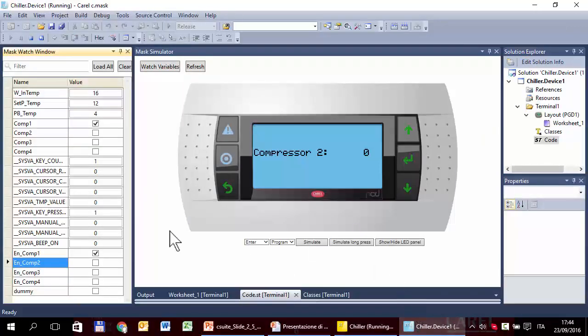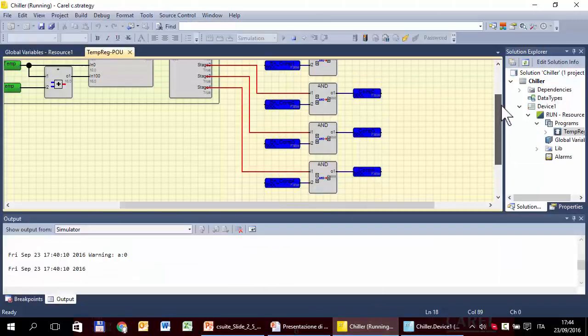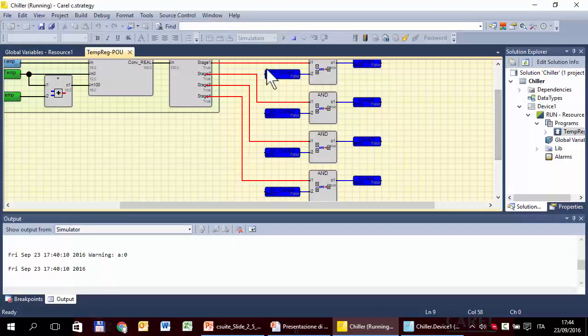Finally, it may not make much sense, but we can disable compressor one as well. If you click up and down, you can see the masks of all four compressors, but all compressors are forced off. We can check this in the strategy too — we have the cooling demand (true, true, true, true, true), but the compressors are off because of the enable.